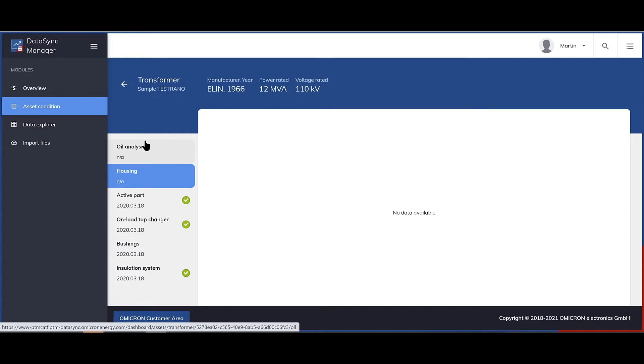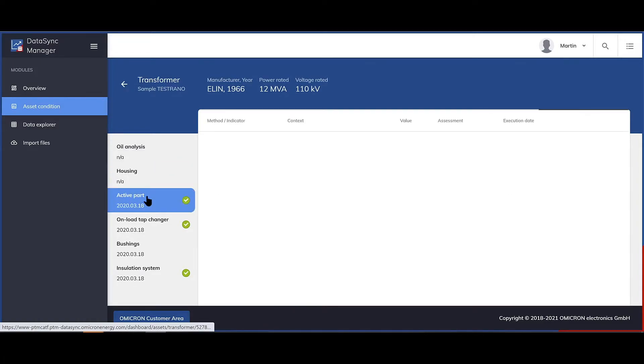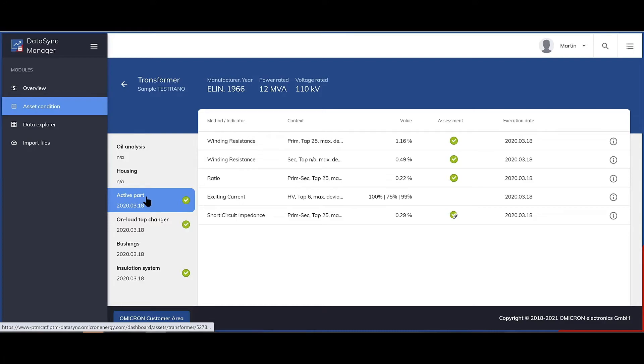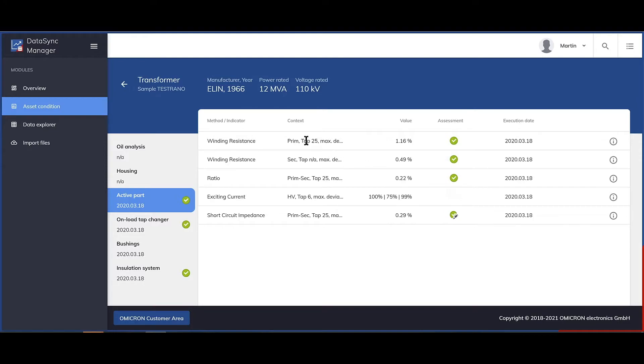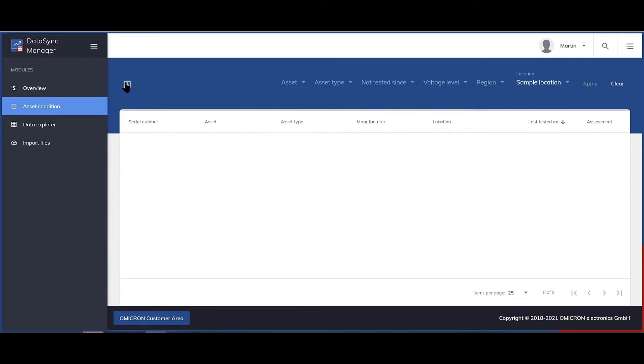Drilling down, we'll show you the testing state. For this transformer, no DGA was taken, no visual inspection is available, but the active part was tested. Last in 2020, the assessment was okay, and the key indicators are shown here.